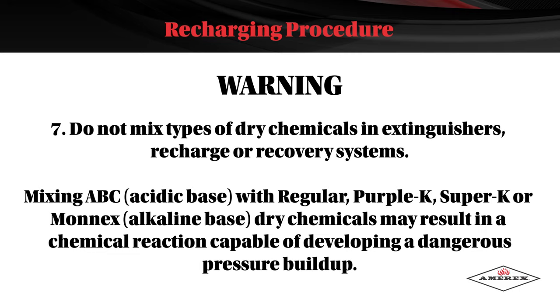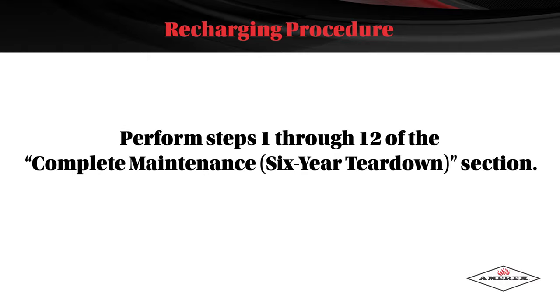Do not mix types of dry chemicals in extinguishers, recharge, or recovery systems. Mixing ABC with regular, Purple K, Super K, or Monnex dry chemicals may result in a chemical reaction capable of developing a dangerous pressure buildup. Perform steps 1 through 12 of the complete maintenance six-year teardown section.